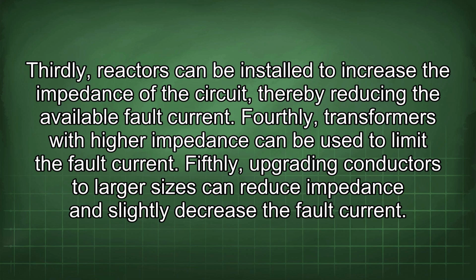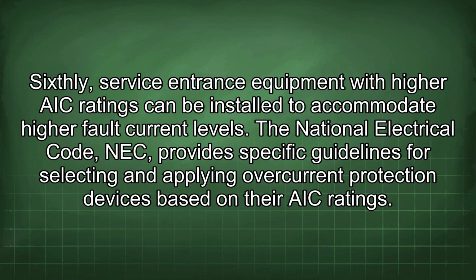Fourthly, transformers with higher impedance can be used to limit the fault current. Fifthly, upgrading conductors to larger sizes can reduce impedance and slightly decrease the fault current. Sixthly, service entrance equipment with higher AIC ratings can be installed to accommodate high fault current levels.